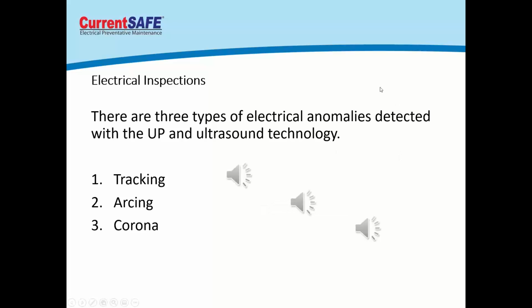Arcing can have tracking with it, which is what you're hearing there as well. But you hear a much more distinct, sustained release of energy, and that's exactly what arcing is. Tracking has reached a point where it can actually discharge over to a grounded surface, and that's arcing. So now we have completed a path.